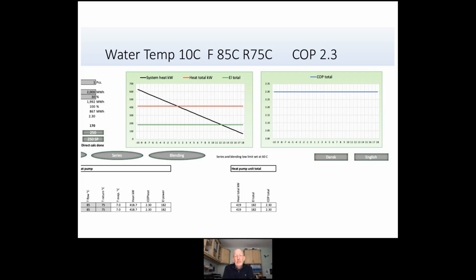is the COP. So with the ground source water temperature, from this example happens to be a mine shaft, it's 10 degrees C, with a flow of 85 and a return of 75, we end up with a COP of 2.3. That is obviously 1 kilowatt of electrical input in and 2.3 kilowatts of thermal energy out.